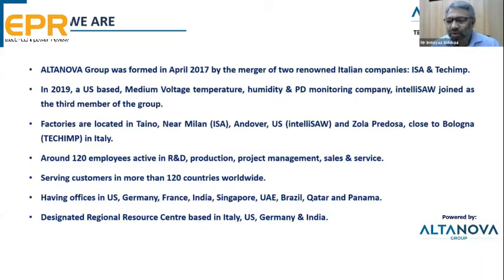So, for example, our equipment can do tan delta monitoring, partial discharge monitoring, and can also take inputs from DGA with the gases coming out because of faults in the transformer. It communicates through our software, and finally we integrate it with their SCADA systems to give pre-information to the OEMs so they can tell their customers what their maintenance strategy should be for maintaining these assets.